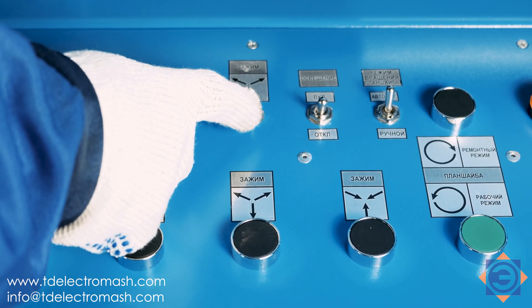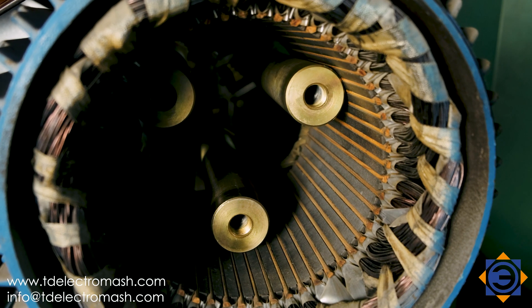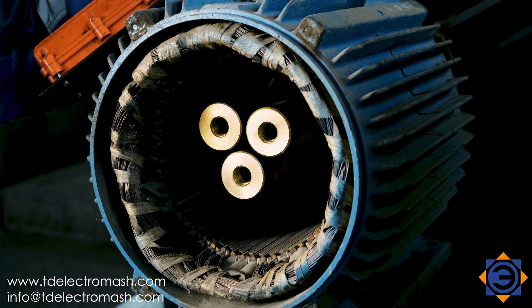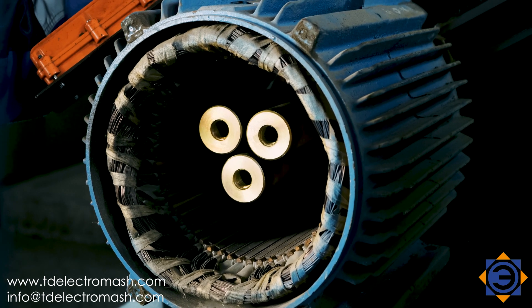Clamp the stator onto the jaws while pressing the switch button. Make sure the pressure control lever is in the down position before clamping. The inside of the stator must be equal distance from the tailstock jaws; otherwise, uniform clamping force will not be achieved.